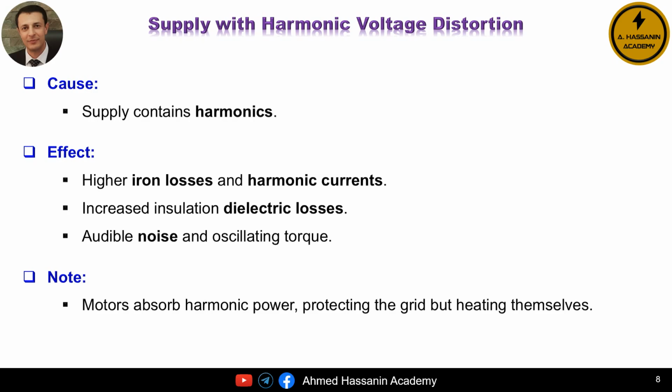Here's the interesting part. Induction motors naturally absorb some of this distorted power, which actually helps protect the rest of the electrical network. But there's a trade-off. The motor itself gets hotter, and that's something we have to watch out for. So in short, harmonics aren't just an electrical nuisance. They directly affect motor heating, torque stability, and noise, and we need to account for that in design and protection.